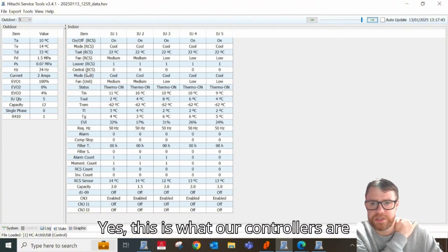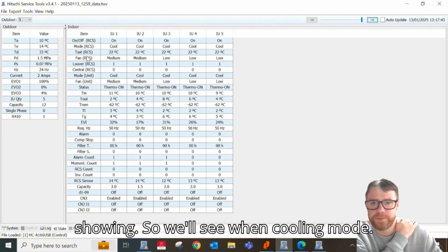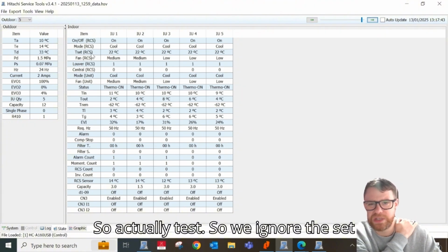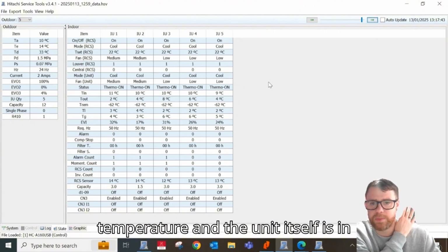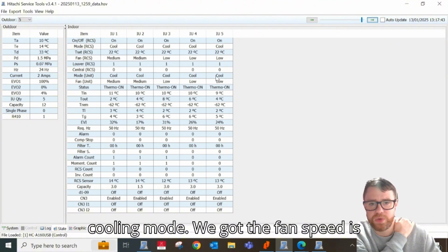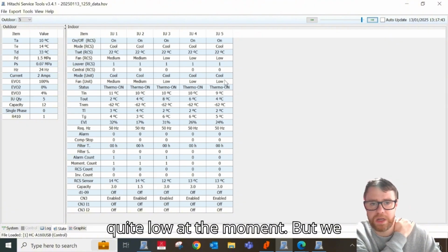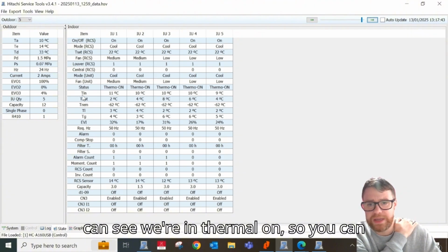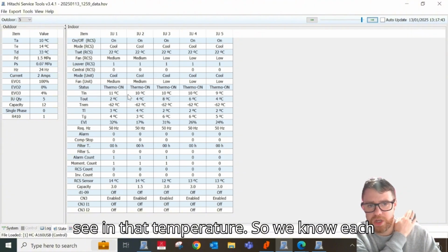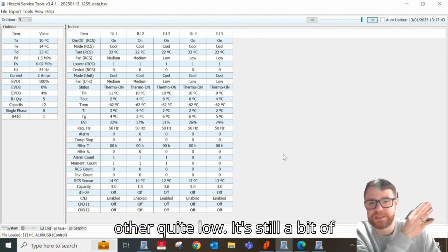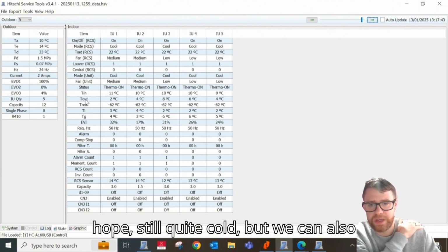Where it says RCS, this is what our controllers are showing. So we can see we're on in cooling mode. We're actually in test, so we ignore the set temperature. And the unit itself is in cooling mode. We've got the fan speeds quite low at the moment, but we can see we're in thermal on. So we can see our inlet temperature, and we know they're quite low. It's still quite cold, but we can also see our outlet temperature.